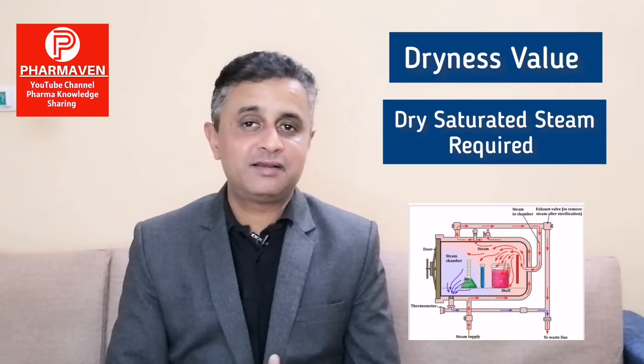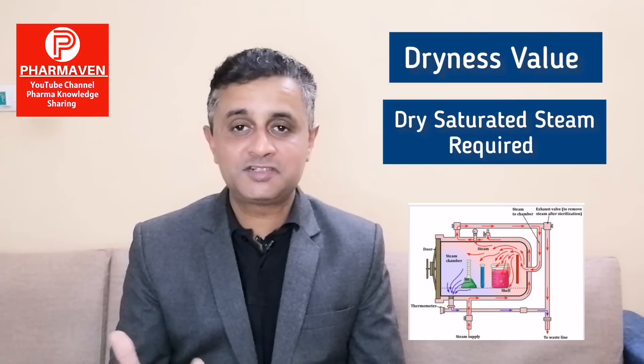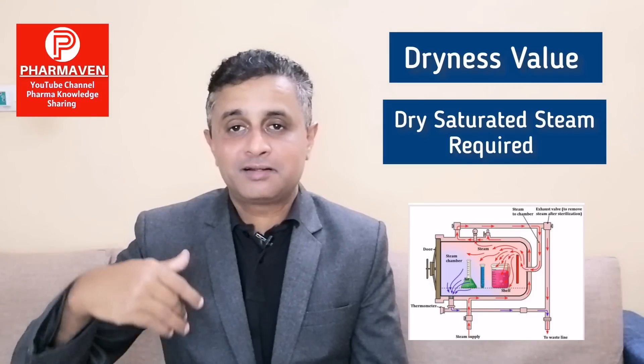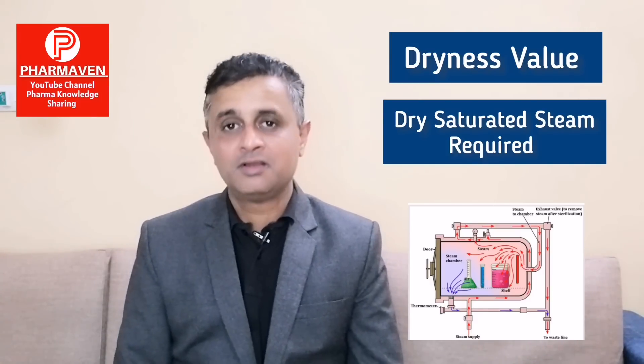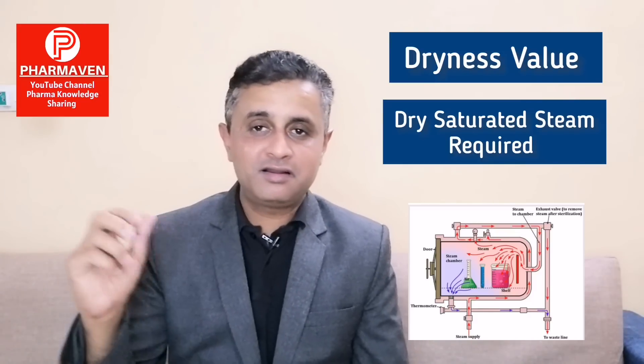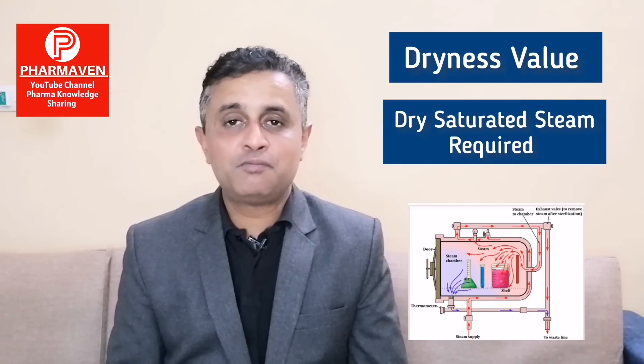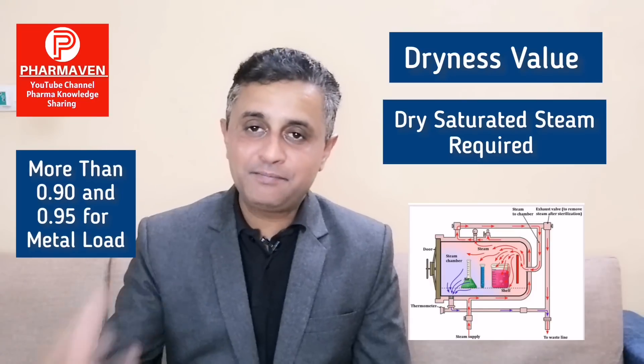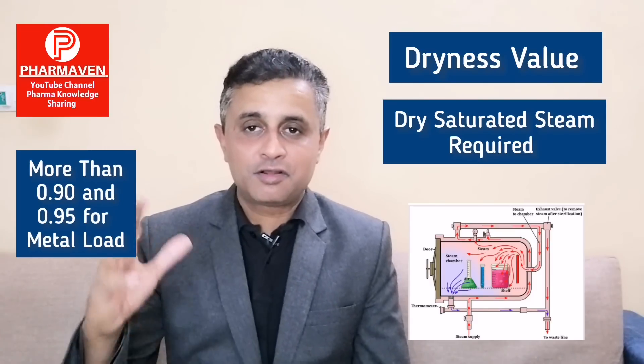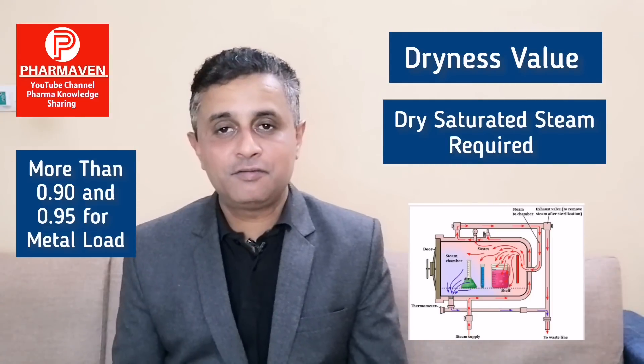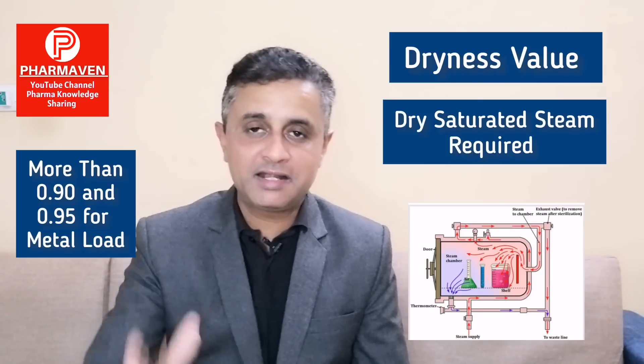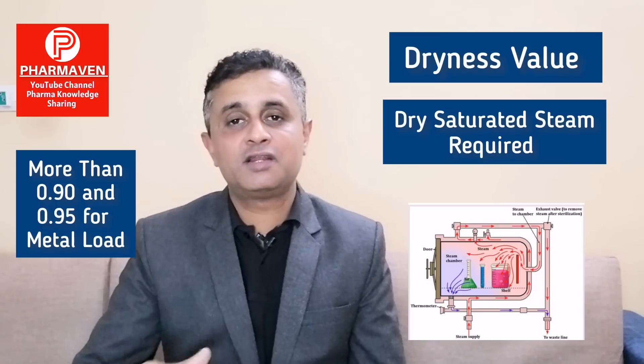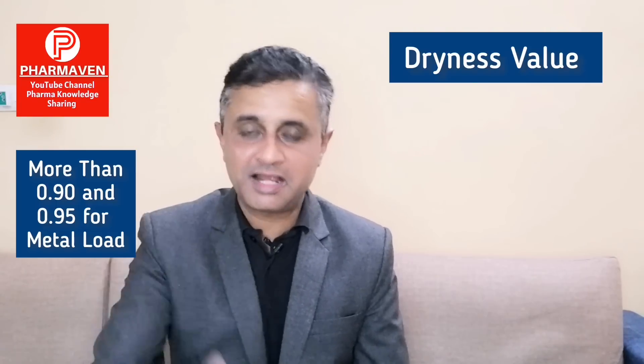We need heat transfer from steam to load to achieve effective sterilization. If steam contains many water droplets it is wet steam — not saturated steam. For that we need dry steam. Dry steam has enough moisture so that it will travel, condense, and transfer the latent heat of vaporization to the load. The acceptance criteria for dryness value is: dryness value should be more than 0.90 for normal loads and more than 0.95 for metal or hard loads. If we consider 1 as the value of dry saturated steam, we need 0.90 for normal loads and more than 0.95 for metal loads.